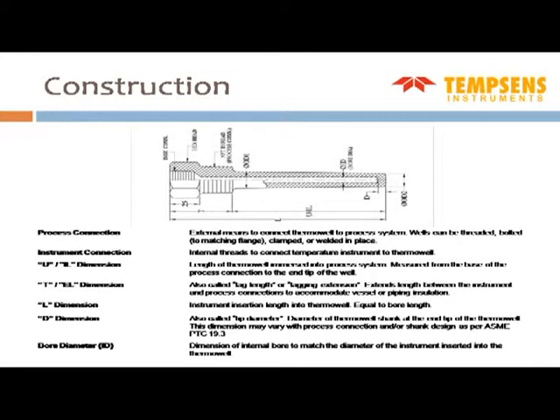There's a process connection which is tightened to the process, and there's an instrument connection which is tightened to the stem or to the insert. So you see on the left hand side, you have the process connection on the threaded portion, and on the top you have the instrument connection. The instrument connection is where the RTD insert would be tightened, and there is a bore which is drilled according to the size of the RTD or the thermocouple, and the outside process connection will be tightened to the process.